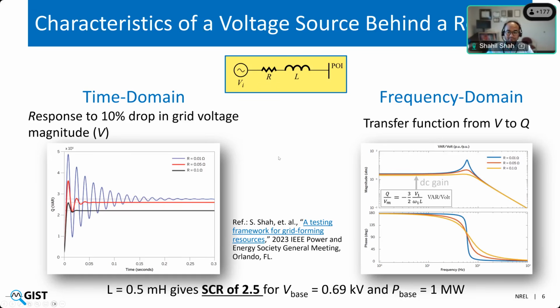So here I'm showing the reactive power response in the time domain for this voltage source behind reactor. Right now we are still talking about all these responses that you see on the screen. They are for this voltage source behind reactor, so it's not any inverter, any generic model or any experimental result. As we see in this response, whenever there is a drop in the voltage at the POI, this voltage source behind reactor will immediately dispatch some reactive power to stabilize the voltage at the point of interconnection. The amount of response is going to be inversely proportional to the magnitude of impedance of the reactor. So if the reactor impedance is large, the amount of response that you will receive from this voltage source behind reactor would be smaller. The second thing is, depending on the resistance of the reactor, the response can be oscillatory or it will be damped. So that is looking at the voltage source behavior within the time domain.